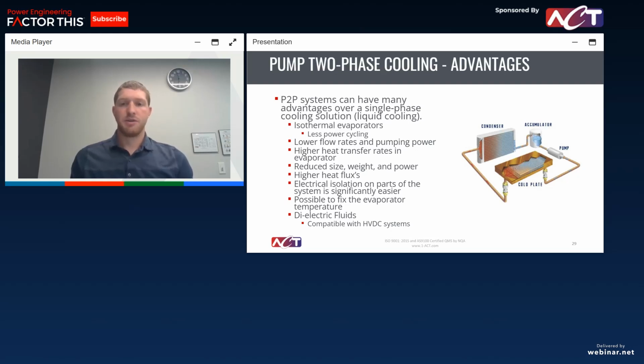That's something that can be controlled and set, and there's a lot of control in that in the design. So if you say I need all these components to be held at 65C, you can design that in and set that, and they'll all be right at that, within a degree or so, compared to single phase where oftentimes you'll have a 10 degree, 15 degree delta across the cold plate. And so that also leads into less power cycling of your components, longer lifespan for those electrical components.